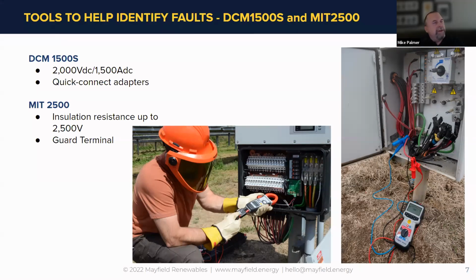Well, I was thinking while you were talking that inverter diagnostics have gotten light years better than where we were 25 years ago. They're better, but they still don't nail where the trouble is. And our PV technicians, give them credit, have their sequence of ways to find these faults. I think it's all about sectionalizing and using what's in your toolbox to do that. You hit on all the points, but I'm always amazed that at conferences, and of course NABCEP, when we talk about the guard terminal, how many people have never used it. You don't need to use it unless you have to, and when you have to, it can really save the day.